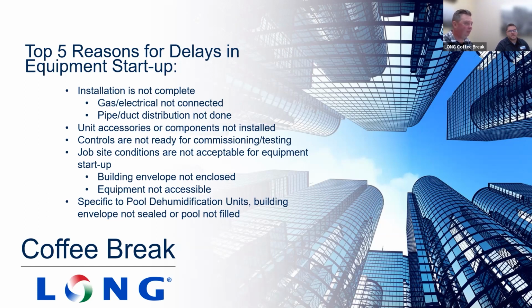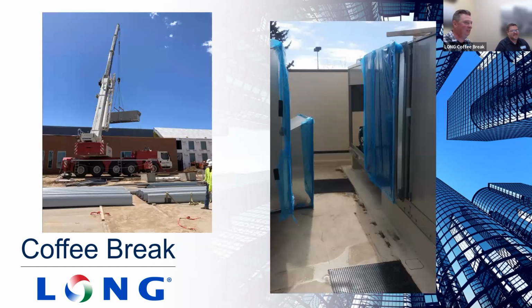That's when the startup should be occurring, after the equipment's installed and everything else is relatively close to completion. Exactly. That's where you're going to get the best protection for the equipment and the best efficiency out of the time necessary to do the startup. We're going to be able to work with the temperature controls contractor to iron out any issues with control sequence and stuff like that before commissioning occurs. Beautiful. So let's go to what I'll call the startup folly reel here, and this is a beauty.